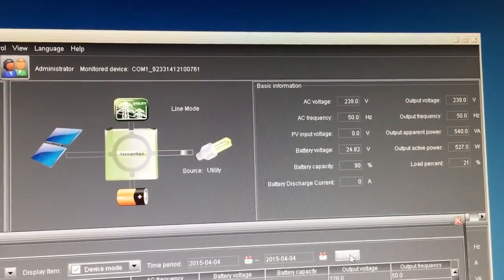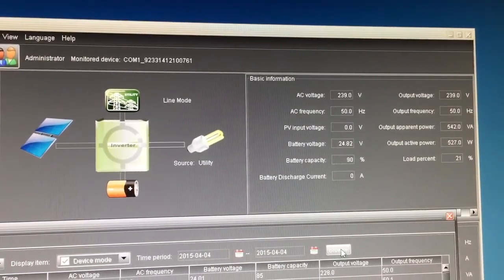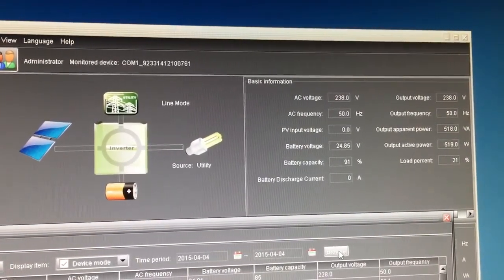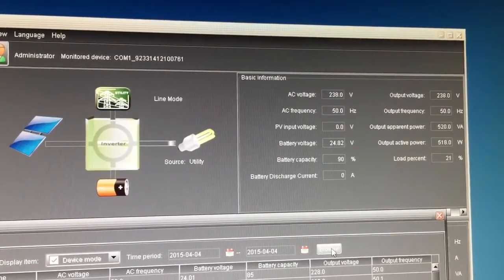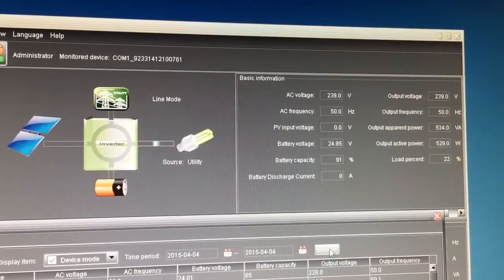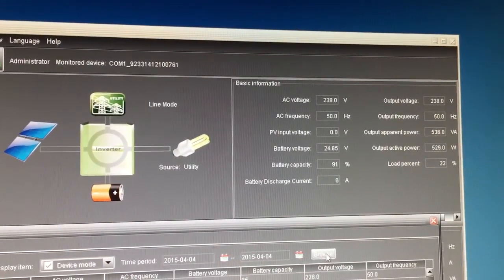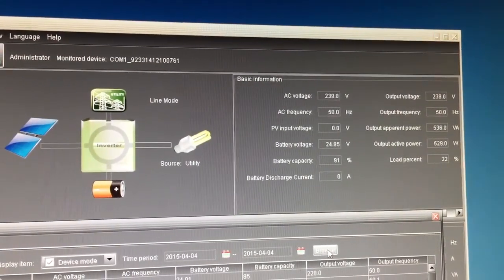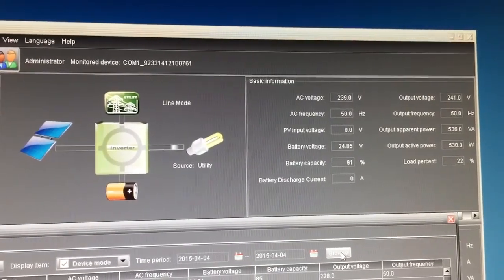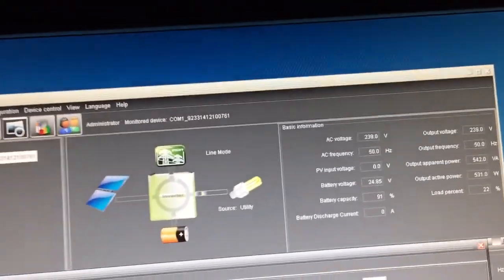That's disappointing. I wonder if it's because the battery voltage went so low. The battery voltage, I think, went down to 22 volts or something. It's pulling 110 amps or somewhere around that, give or take. Might have clicked back over to line mode just because of the battery, I think. So it's not going to go back again. That's disappointing. Well, it's not really. I mean, it's a good test.